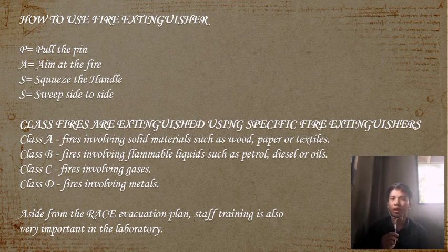First step, pull the pin. This will allow you to discharge the extinguisher. Second step, aim at the fire. Aim at the base of the fire. If you aim at the flames, which is frequently the temptation, the extinguishing agent will fly right through and do no good. You want to hit the fuel.